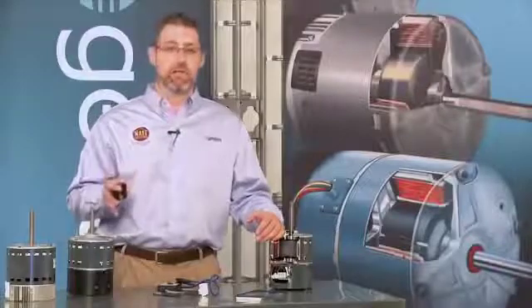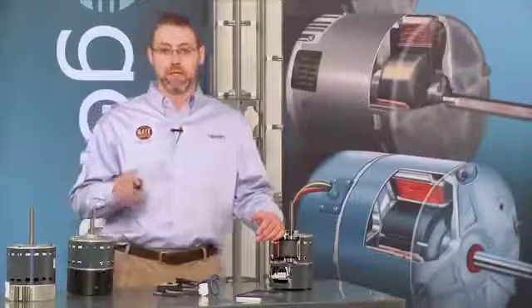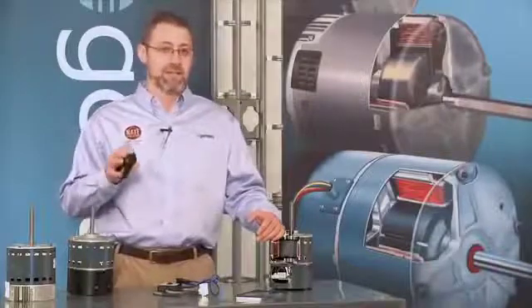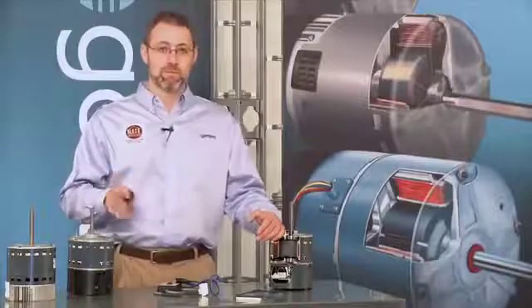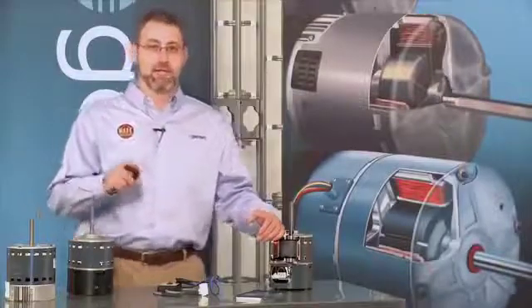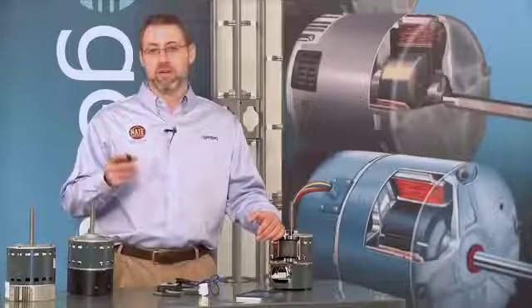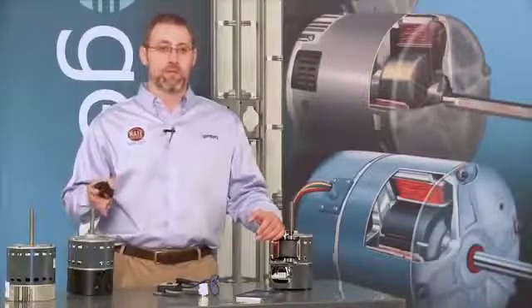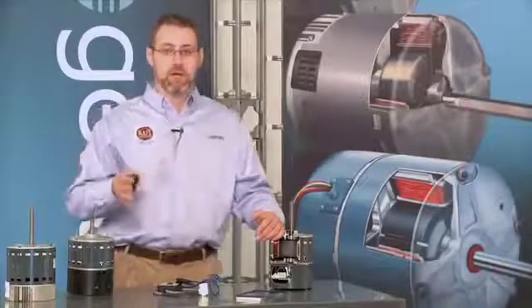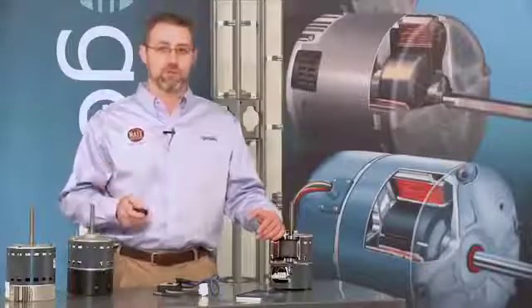Now, we are talking about electrical efficiency here, but that also goes toward the reliability of the variable speed motor, because since it has less heat to dissipate, it runs cooler. So let's get back to the electrical efficiency. Now keep in mind that the average heating and cooling system runs about 3,500 hours, national average for the United States. While we're making the same airflow as a PSC motor, our electrical efficiency gain is around 20 to 25%.